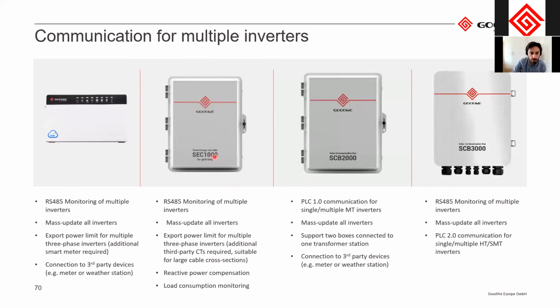And with this one, you can also realize export power limit for multiple inverters, and then you use third-party CTs. It's very common that some use the GoodWe CTs that are delivered with the residential inverters or the storage inverters, and then they try to connect it to this one in CNI applications, but those current transformers don't work with this one. For this one, you will need third-party CTs that have 5 amps on the secondary side. So this one is for CNI and utility, and this one is for residential application.